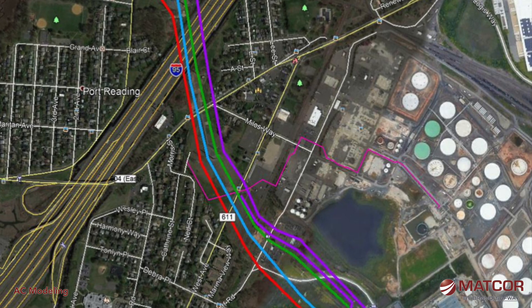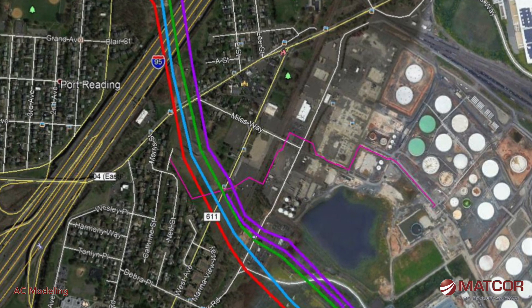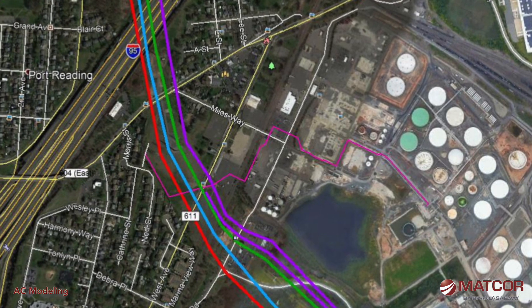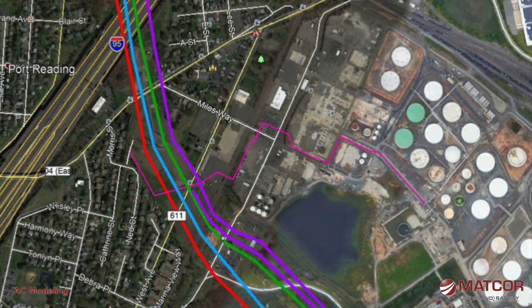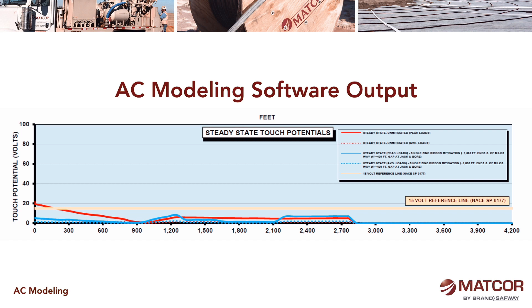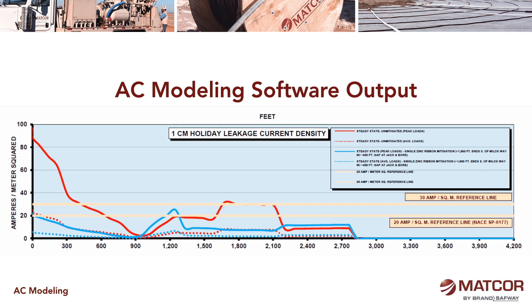Here's an example of a model where you've got multiple high voltage transmission lines and a pipeline going from one location out to a terminal. We have to model each one of those AC lines and the pipeline's characteristics. Ultimately the output shows you along the length of the pipeline those areas of concern — steady state touch potentials for safety above 15 volts, one-centimeter holiday leakage current for AC induced corrosion, and areas where fault currents can exceed the maximum allowable for coating stress.